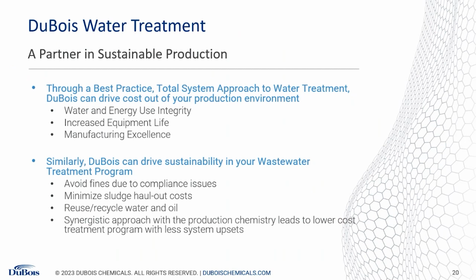So in summary, through best practices, DuBois can use a total system approach to water treatment to drive costs out of the production environment. Water and energy use integrity helps both the environment and your environmental goals, but also drives costs down. We can increase equipment life, have less downtime for repairs by preventing scale and corrosion, and promote manufacturing excellence by having high quality water available when you need it. We can do the same in wastewater: hidden costs include fines due to compliance issues, so we design systems to avoid that, minimize sludge haul-out costs, and reuse and recycle water and oil. That synergistic approach between upfront production chemistry and back-end wastewater chemistry can really drive cost savings throughout the entire system.